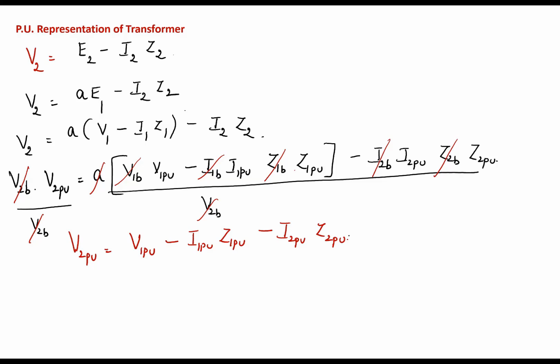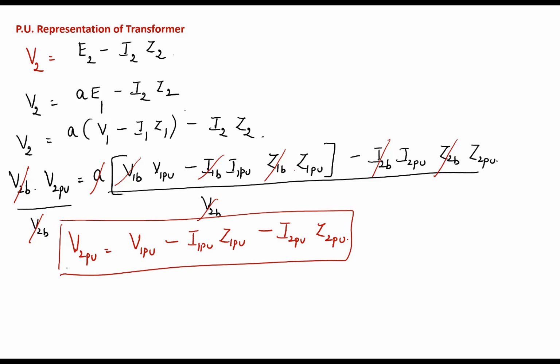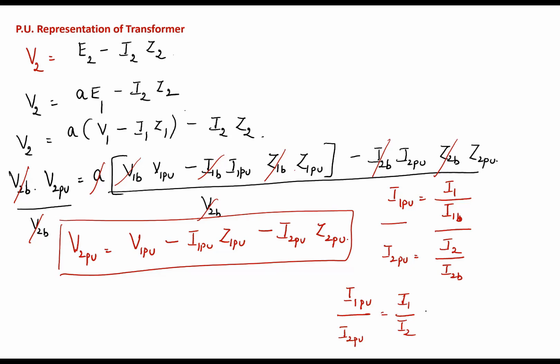So every value came in terms of per unit. Okay, V2 per unit equals V1 per unit minus I1 per unit into Z1 per unit minus I2 per unit into Z2 per unit. This is the second relationship. Now, I1 per unit I can write as actual I1 value divided by I1 base. Similarly, I2 per unit I can write as actual I2 value divided by I2 base. So if you divide one by the other, I1 per unit divided by I2 per unit is equal to I1 by I2 into I2 base divided by I1 base.